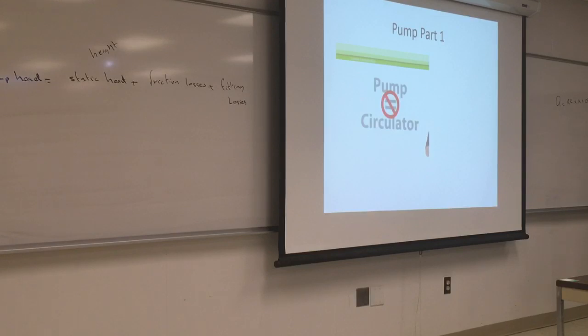It's important to make that distinction between a pump and a circulator, especially since we'll be discussing circulators that are used mainly in pressurized loop systems, systems like hydronic heating, radiant floor heating, or domestic hot water recirculation. Now, we're not talking about multi-stage, multi-impeller-style well pumps designed to lift water a few hundred feet out of the ground. This is a distinction that makes a difference when sizing or selecting a circulator for your hydronic system, as we'll see later on.